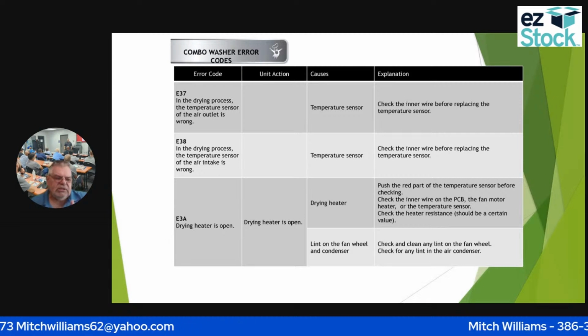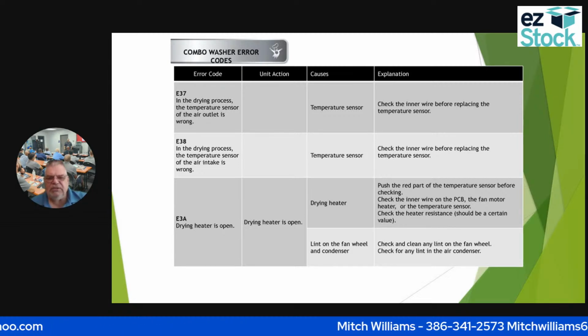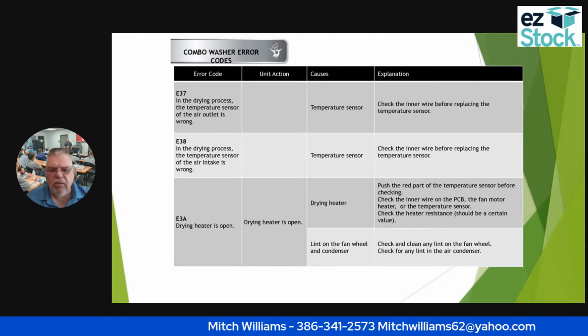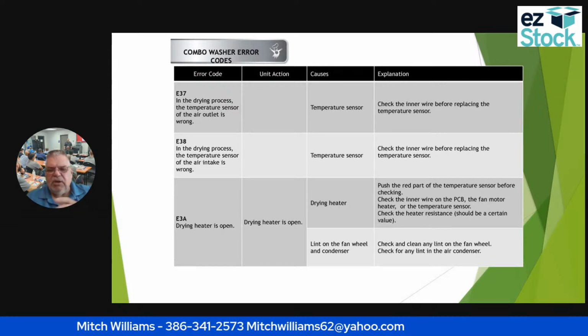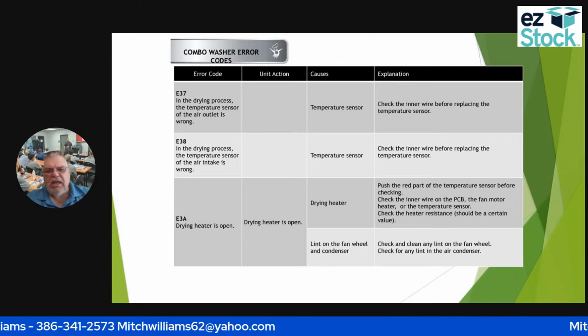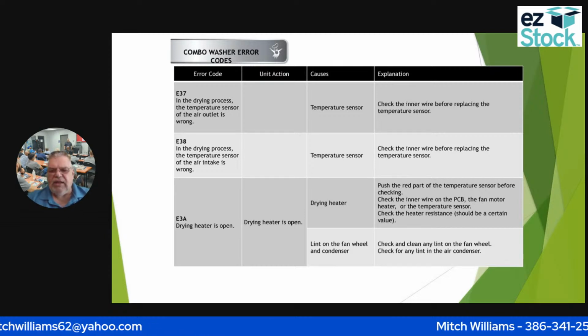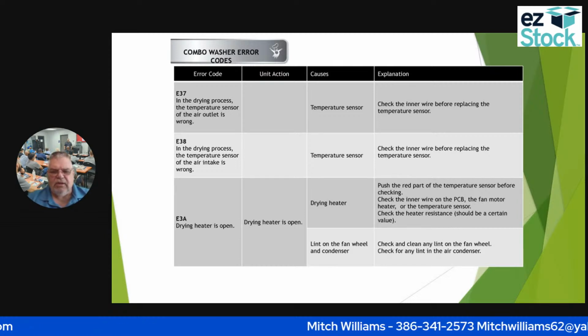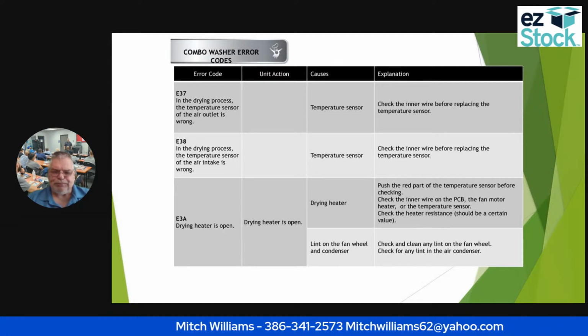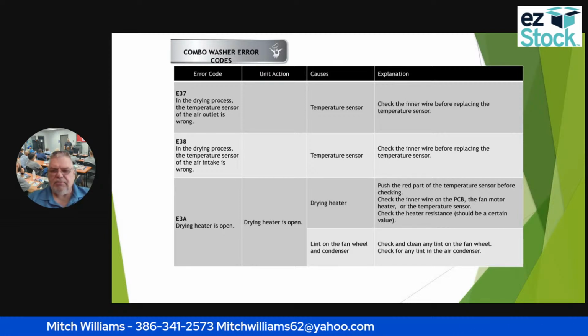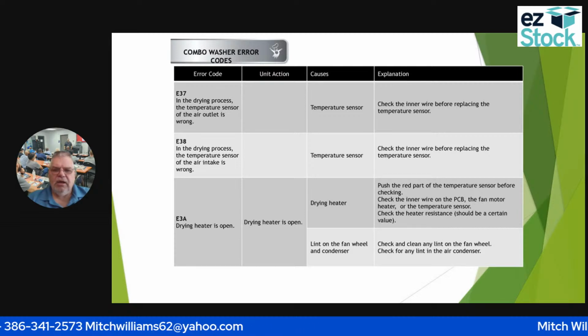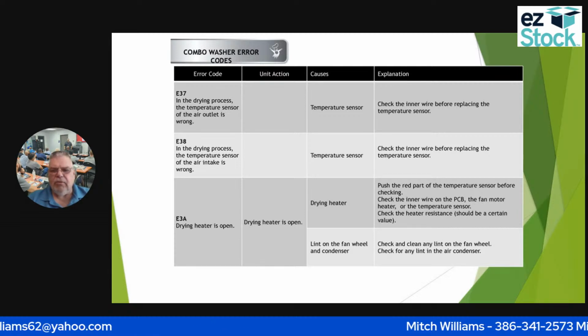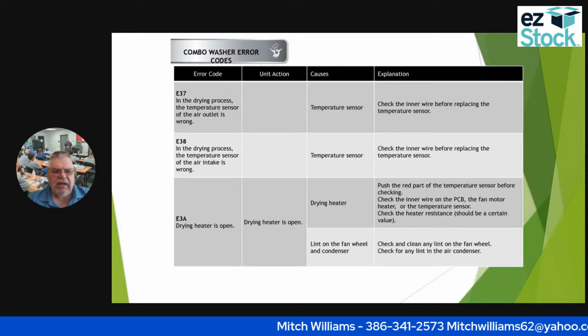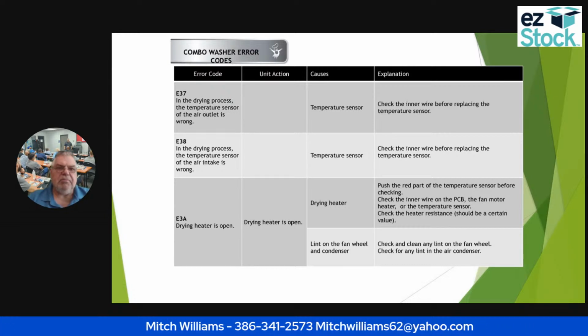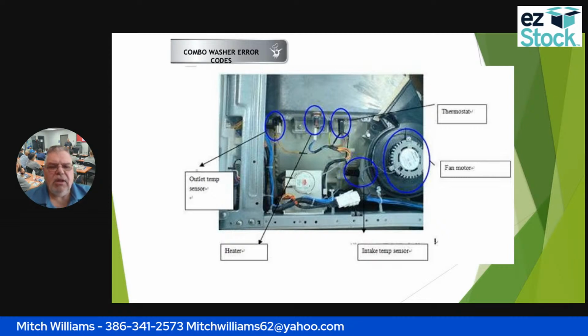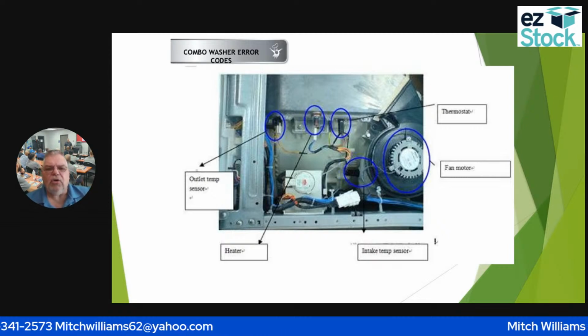One of the other things that's common for this unit is there may be lint on the fan wheel or the condenser of it. So that could be that E3A. So I need to check that. If all of that checks out, I'm going to check the lint on the fan wheel and the condenser. Right. So after I've checked all of that and it's good, I'm going to have to go back. If you go through all these and I still got an E3A, I'm probably going to have to replace that board.